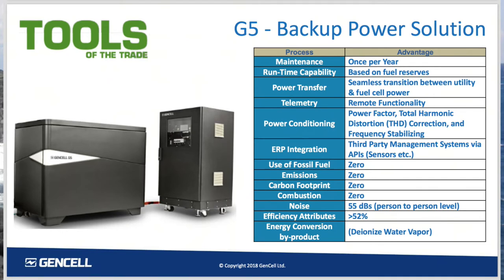If you think of a UPS that has a definable amount of energy stored in batteries, it will only give you a certain amount of runtime for your equipment based on that battery storage. The more batteries you have, the more runtime you'll get. The problem is that it's a stored energy device, not a generation of energy device. So when you're talking about a long duration application needing more runtime than typically 45 minutes to an hour, that becomes a big problem, because once that energy is consumed, there's no way to replace it unless you hook up some other device that will generate energy to recharge those batteries.